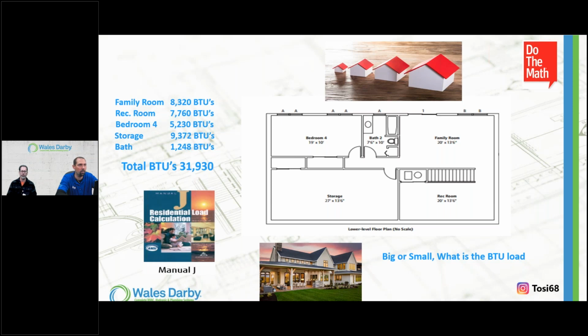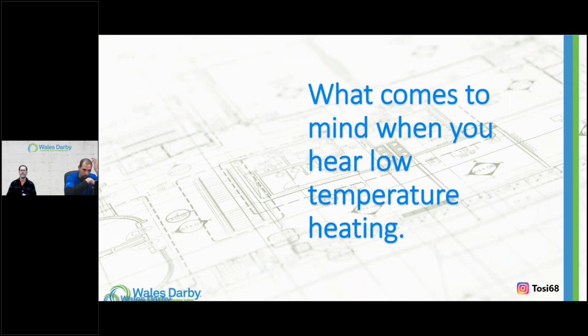What is our source? What's our boiler? What's our heat pump? Air source, air to water, geothermal even, there are so many factors, even just electric baseboard. But big or small, it's not just throwing a cookie cutter BTU per square foot at it. It could get you in trouble. You could be oversizing, you could be short cycling, with no steady state of efficiency. And we had a conversation before with the gentleman, talking about the load calc and stuff like that, and he made a good point.